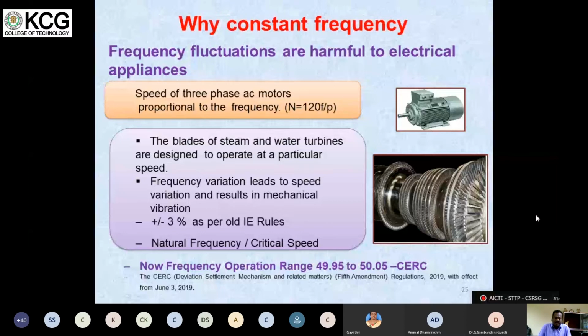But what is to be maintained for the grid frequency is different. The frequency operating range now is 49.95 to 50.05 as per the CERC regulation 2019. So they have narrowed it down. Earlier it was 49.5, 49.49, and now they have narrowed it down to 49.95 to 50.05. That is the range of frequency operation. So with plus or minus 3%, the equipment can be operated and will not get damaged. At the same time, we should maintain the grid at 49.95 and above, and less than 50.05.